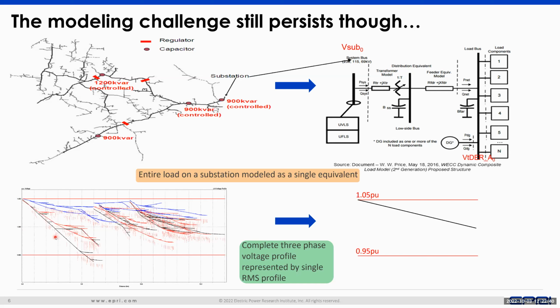Now, say you had a DER that is going to trip at a voltage of 1 per unit. DER don't trip at 1 per unit, they trip at 0.9 or 0.8 kind of voltage level. But given that we have this plot of voltage here, let's assume that they trip at 1 per unit. Then what will essentially happen on this feeder is that any DER located at a node which has voltage greater than 1 per unit will not trip, and any DER located at a node which has voltage less than 1 per unit will trip.